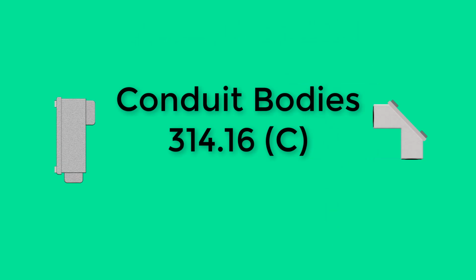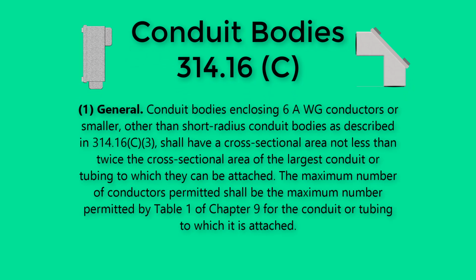Conductor fill requirements are also applied to conduit bodies. Article 314.16(C) addresses conduit bodies. 314.16(C)(1) states, conduit bodies enclosing 6 AWG conductors or smaller, other than short radius conduit bodies as described in 314.16(C)(3), shall have a cross-sectional area not less than twice the cross-sectional area of the largest conduit or tubing to which they can be attached. The maximum number of conductors permitted shall be the maximum number permitted by Table 1 of Chapter 9 for the conduit or tubing to which it is attached.